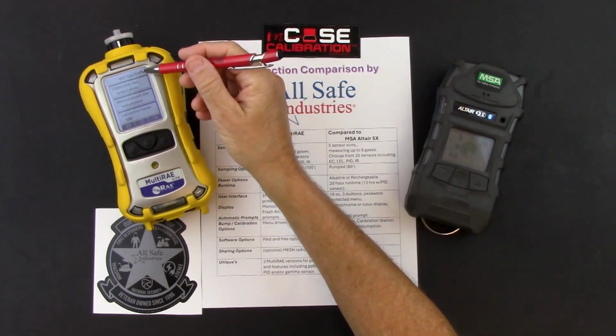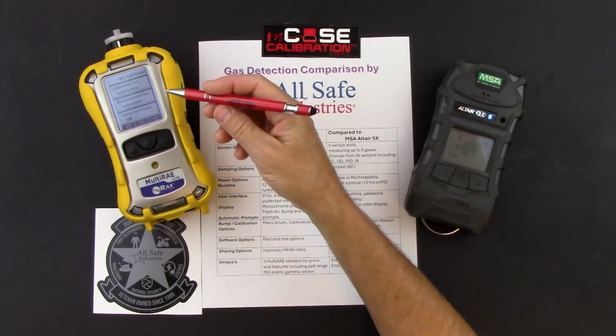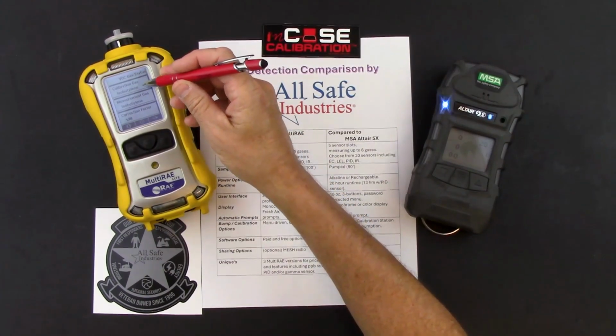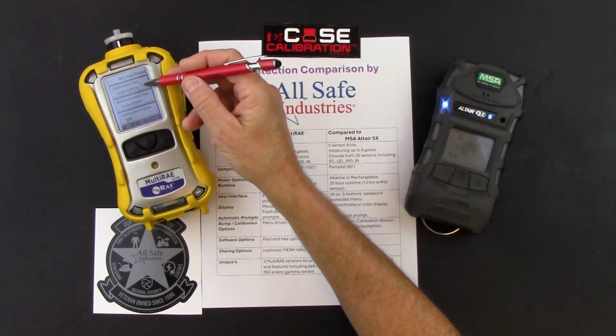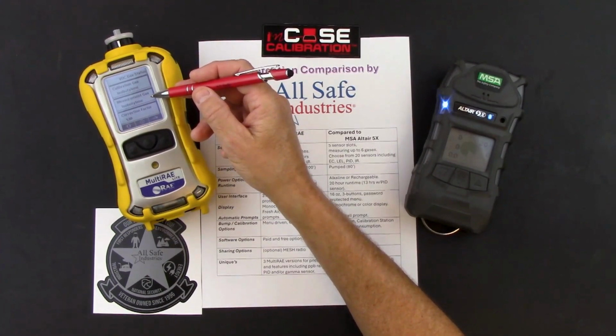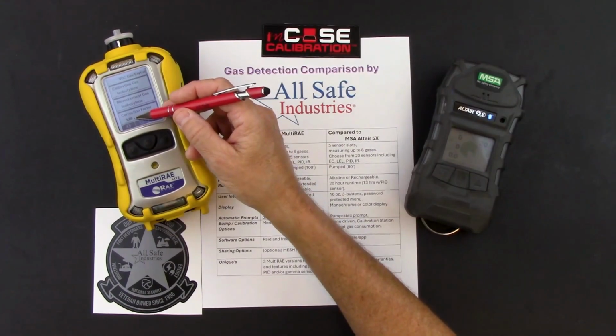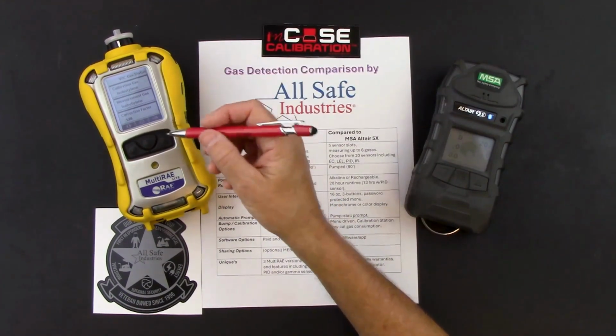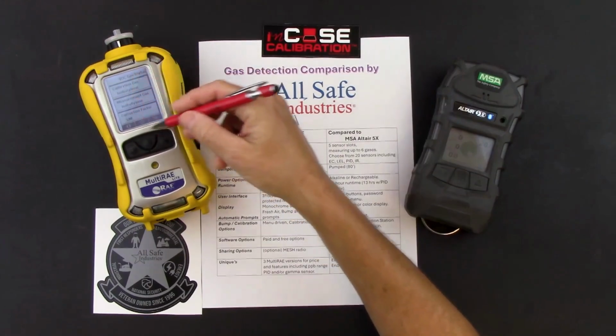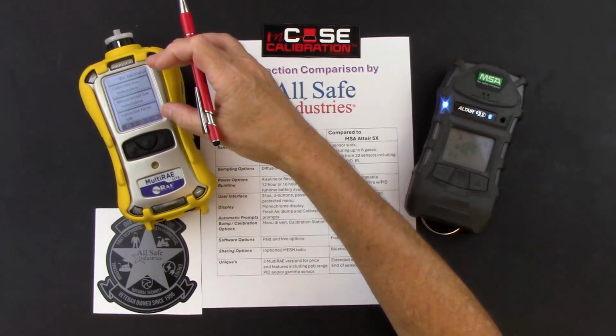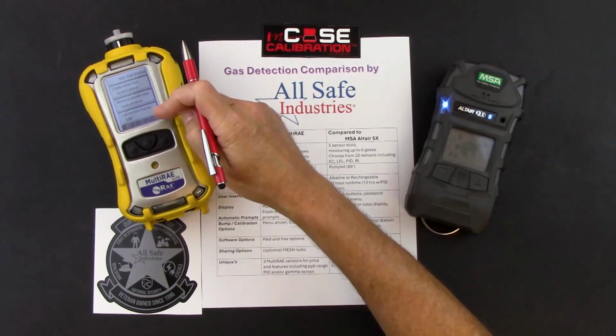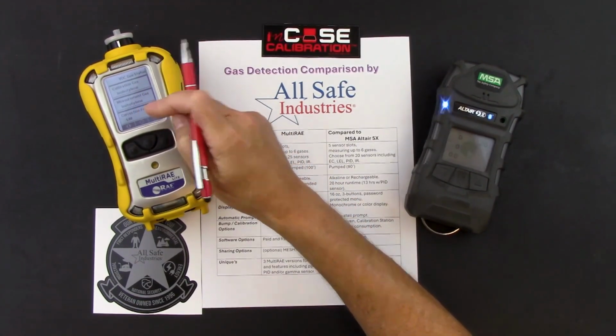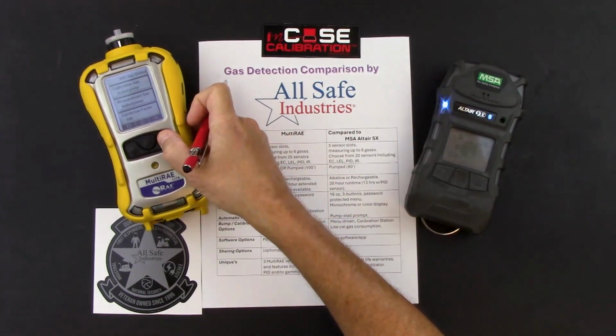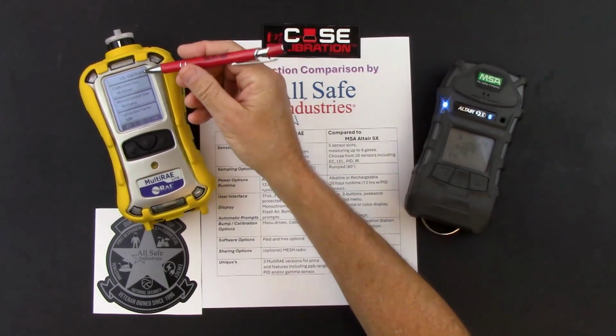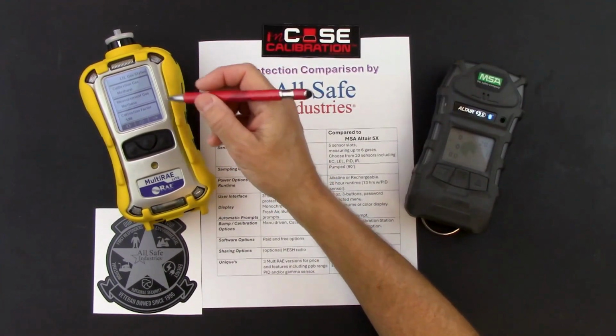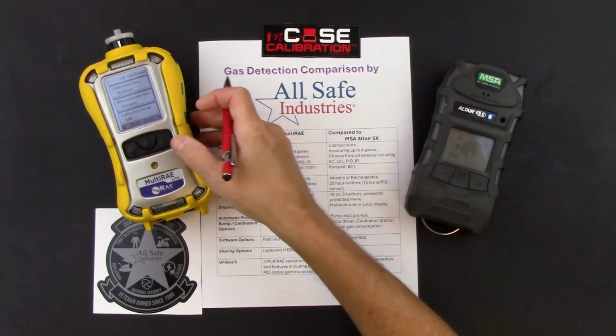And then I love this page here, VOC gas status. This is reminding me that my calibration gas for my VOC sensor was isobutylene. My measurement gas is set to isobutylene. Therefore, my correction factor is a 1. Any number times 1 is the same number. And so there's really no correction factor applied here. If I go into the onboard VOC library and change my measurement gas, you'll see the corresponding correction factor on this screen. I can do the same thing for my LEL gas sensor. My calibration gas is methane, my measurement gas is methane, therefore my correction factor is a 1.